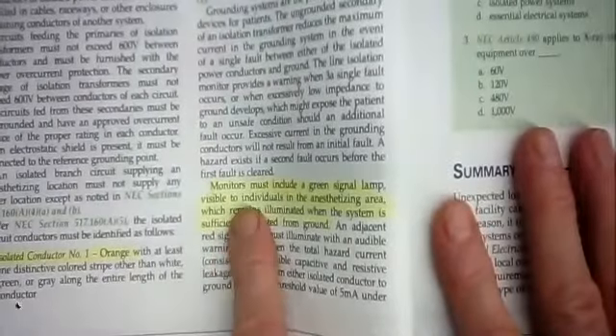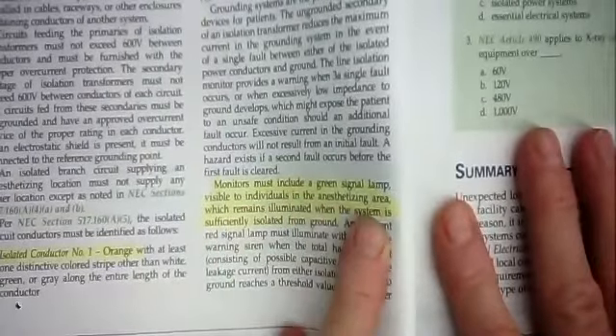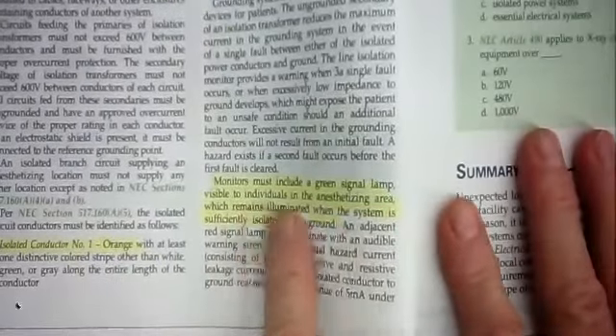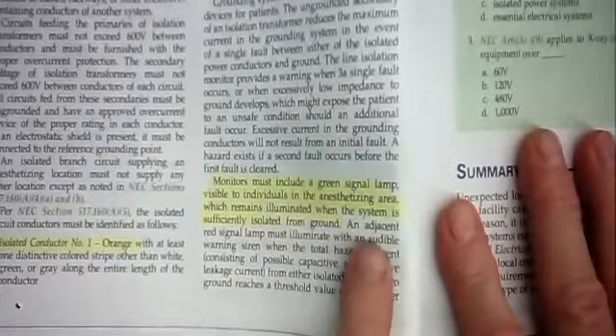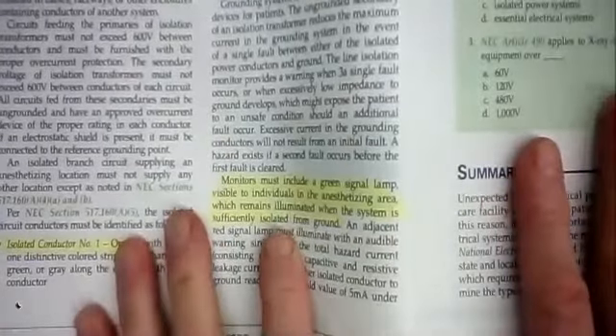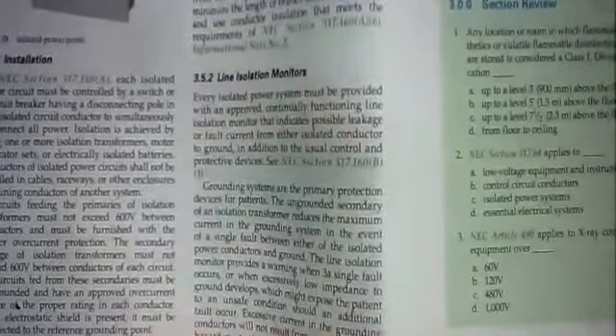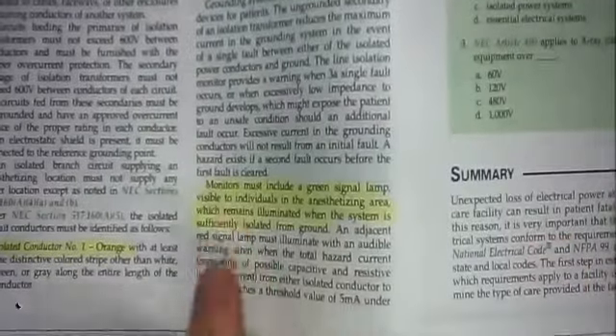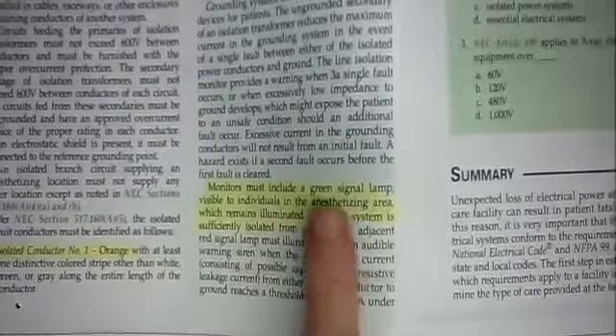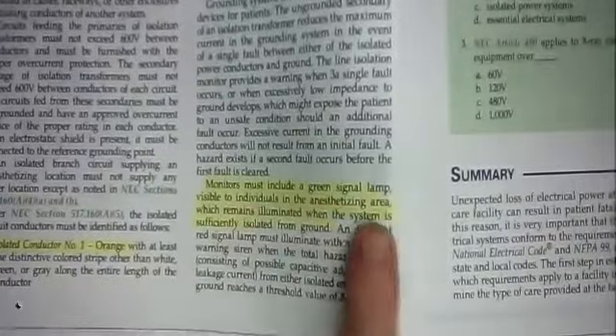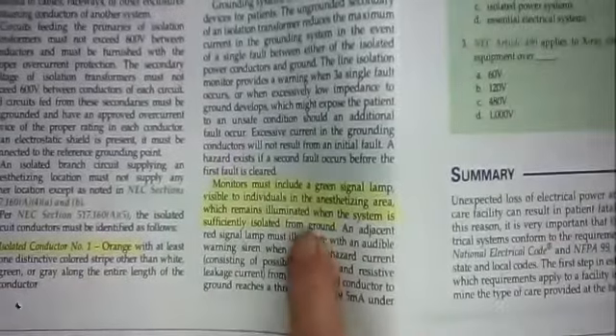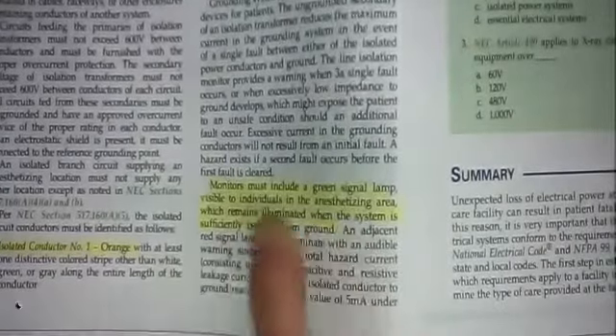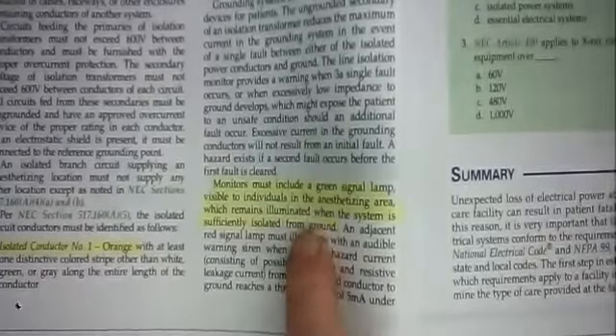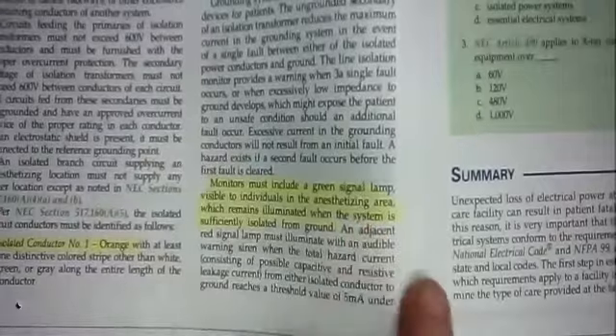And then down at the very bottom of the right-hand column on page 24 says monitors must include a green signal lamp visible to individuals in the anesthetizing area, which remains illuminated when the system is sufficiently isolated. This is anesthetizing equipment and it's isolated from ground, line isolation monitors. You isolate that equipment from ground and there's a green light that's on while it is isolated from ground. If that green light goes out, they have to stop what they're doing and figure out why. They cannot allow it to be grounded in the operating room, because if it's grounded, there could be a spark, and if there's a spark, there could be a boom.